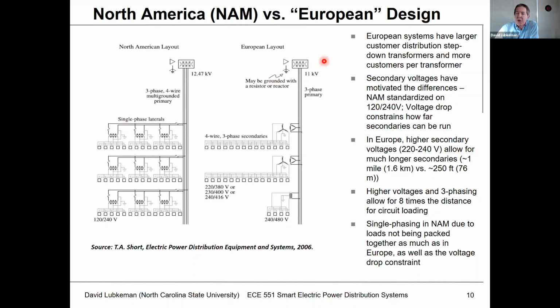If you talk about more of a European design, they run three-phase everywhere, and the reason they can do that is because the loads are more dense - more compacted together. So instead of running these long single-phase laterals, you run three-phase. And because you're running three-phase, you're probably going to want to connect more customers up to these distribution transformers. So in the United States you have a lot of single-phase transformers, while in European systems and other parts of the world you'd see more three-phase transformers.